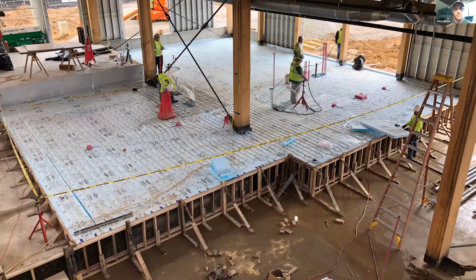One of the most interesting aspects of the net positive energy is our radiant flooring. This is a photograph of PEX tubing going into the floor. What you see here is a slab on grade, the first level, which steps up a few times. There's blue board insulation on top of the slab on grade, and then PEX tubing on 6-inch centers attached to that insulation, with 3 inches of concrete poured on top.